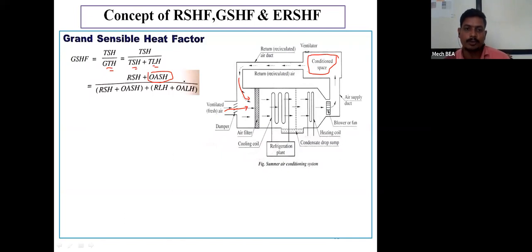So here, if I consider the sensible heat and latent heat which are introduced because of mixing the outside air, that will be called the total sensible heat. Total sensible heat is nothing but room sensible heat plus outside air sensible heat, and total latent heat is nothing but room latent heat plus outside air latent heat. So the grand total heat is nothing but total sensible heat and total latent heat.